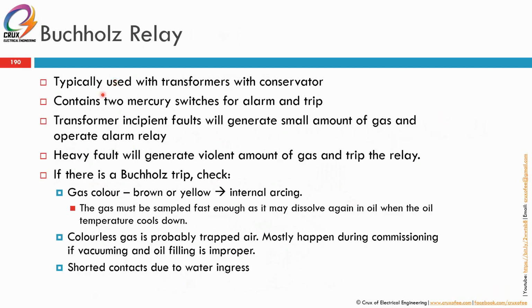So next on the mechanical protection is the Buchholz relay. Always remember Buchholz with a double H. It is typically used with transformers with a conservator tank. It contains two mercury switches for alarm and trip. Transformer incipient faults will generate a small amount of gas and operate the alarm relay, while heavier faults will generate a violent amount of gas and trip the relay almost instantaneously.